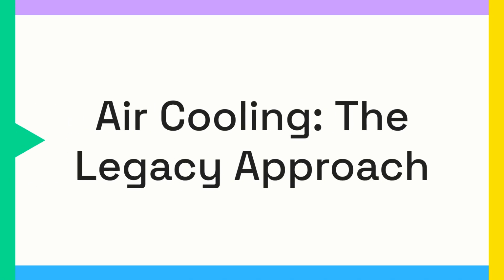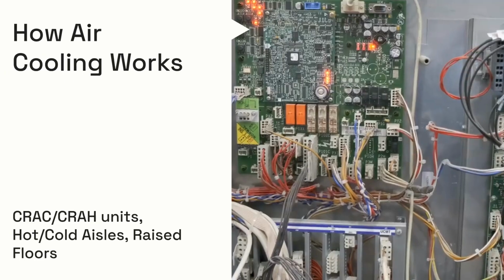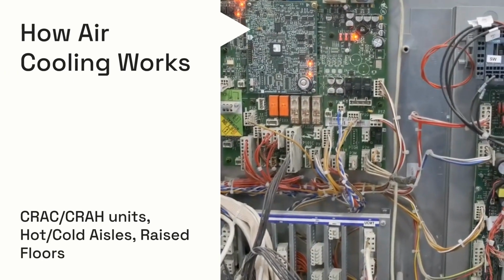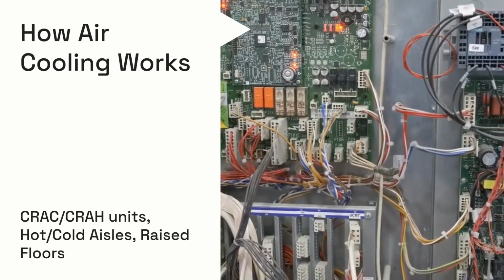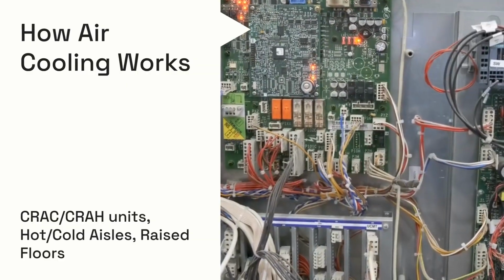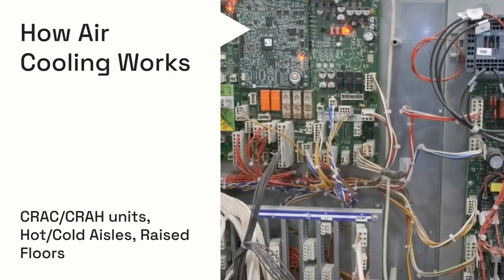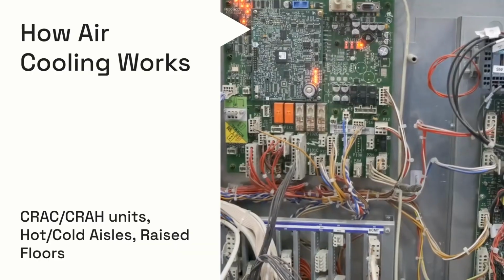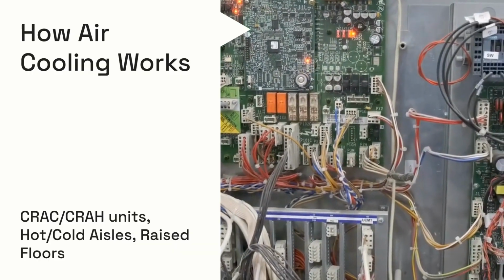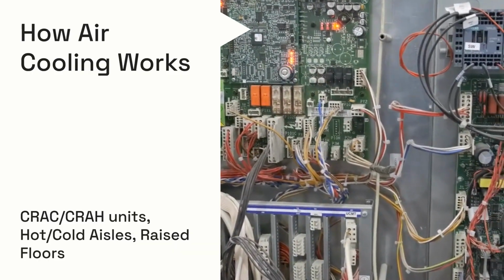For decades, air cooling has been the backbone of data center thermal management. It's well understood and widely implemented, but it faces fundamental limitations in the era of high-density computing. Air cooling relies on moving large volumes of air to dissipate heat. Systems like CRAC and CRAH units condition the air, which is then distributed through hot/cold aisle containment setups. This method is pervasive in legacy data centers, but struggles with high heat loads.